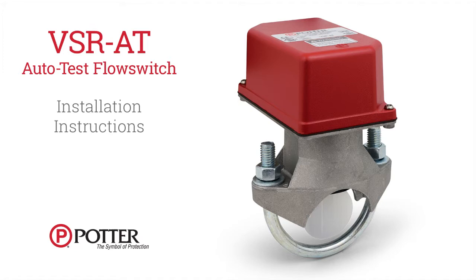The VSRAT is a UL listed and FM approved flow switch that incorporates an electronic retard with a small motor and proprietary software that allows it to conduct an automatic water flow test without flowing water.